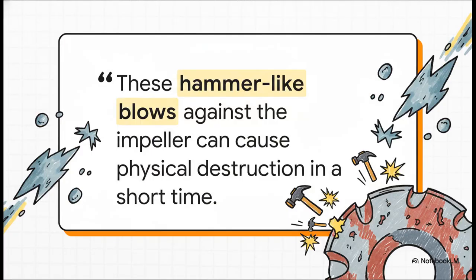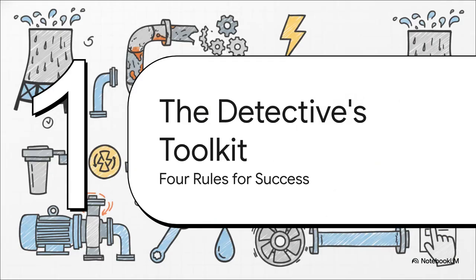As these tiny vapor bubbles move through the pump, the pressure rises again, and they violently collapse. They implode. Each implosion acts like a tiny, focused explosion, delivering a hammer-like blow against the pump's impeller. We're talking millions of these little explosions just eating away at the metal, literally destroying the pump from the inside out. All right, so we've identified our two killers, air and cavitation.